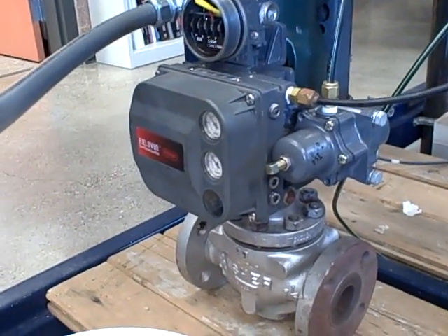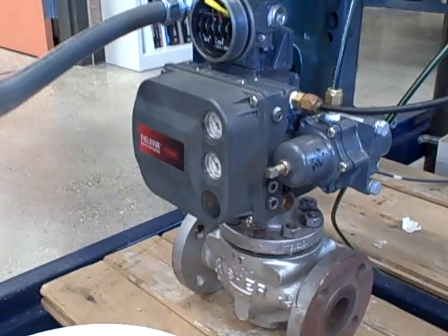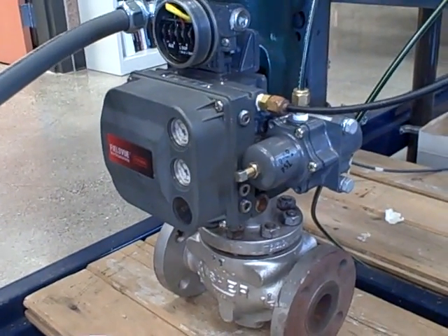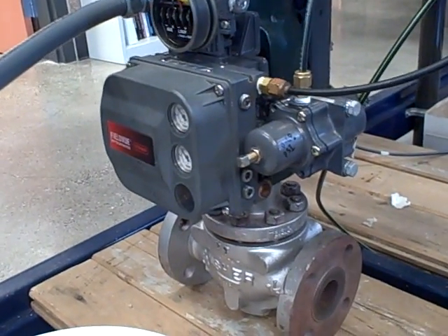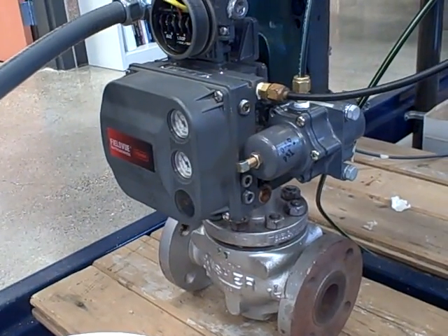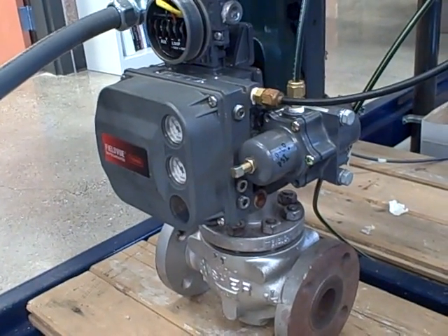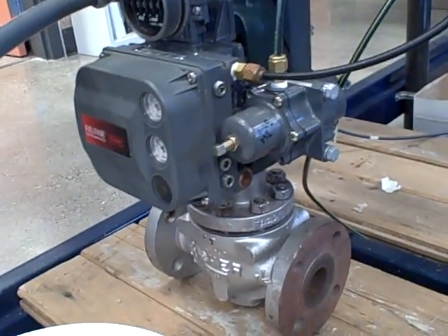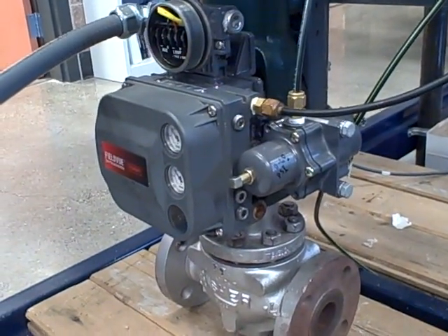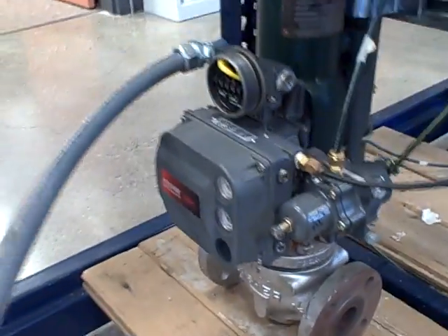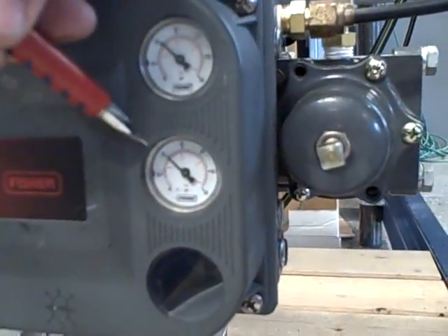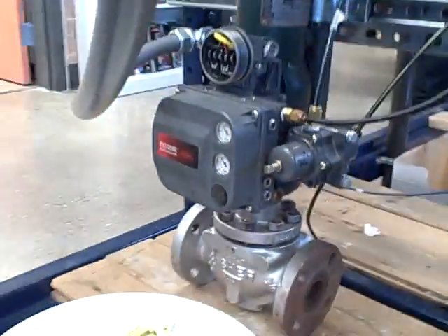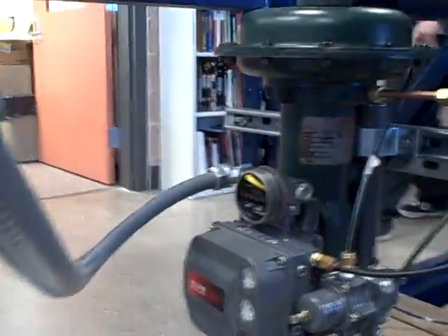I would put some mark on there at least how many PSI of pressure you expect. For example, one of the other teams has a setup where their I2P requires a different pressure source than the positioner. They have a Valtek valve that requires 50 PSI to run the valve, but the I2P only takes 20. So there it's critically important to label the supply pressures because they are different. So in this case, let's take a look at supply pressures. We have on the DVC6000, 20 PSI supply, which stands to reason because the valve has a 3-15 PSI lifting range. Giving you 5 PSI extra. Right.